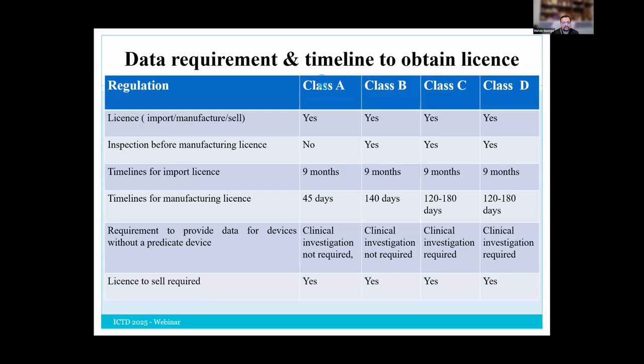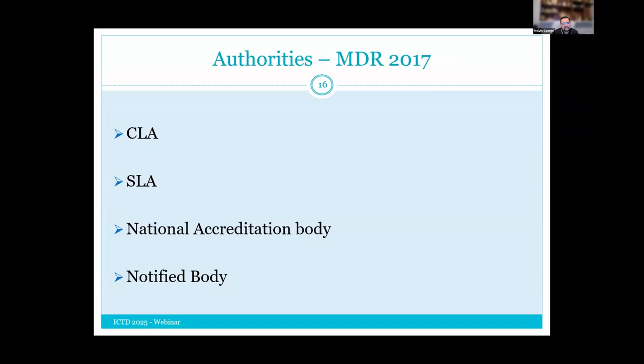Apart from that, if you're coming out with a new device and, according to you, it belongs to one particular class, you cannot just go ahead and project it as a class C or class B device. We would need to get that also approved by the CDSCO, and they need to tell us which class our novel device comes under, if it is a device which does not have any predicate. So this I told you: central licensing authority, state licensing authority, and we have a national accreditation body which certifies the notified bodies on going and regulating sites which manufacture medical devices.